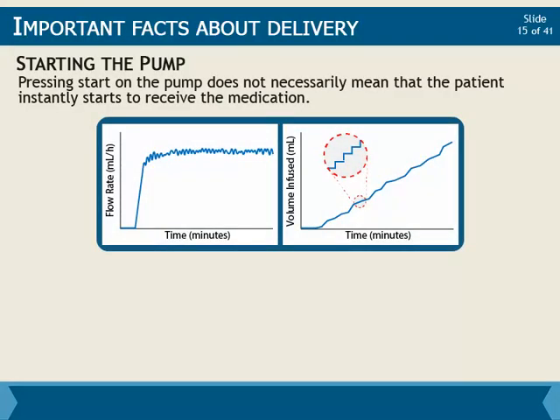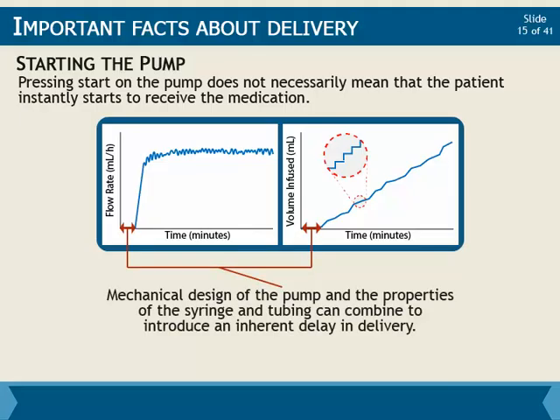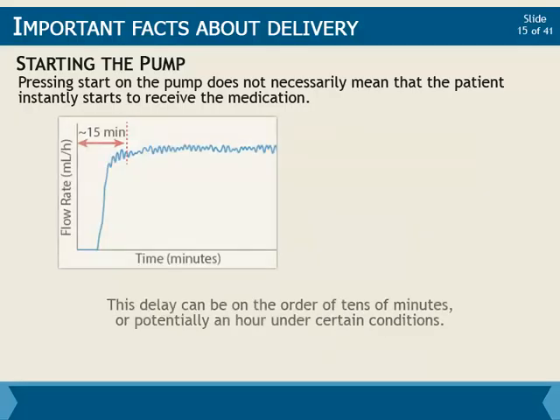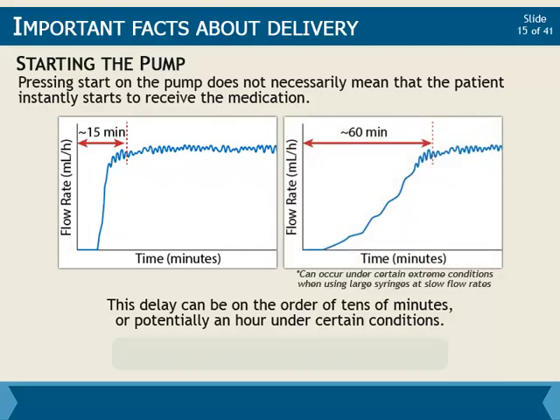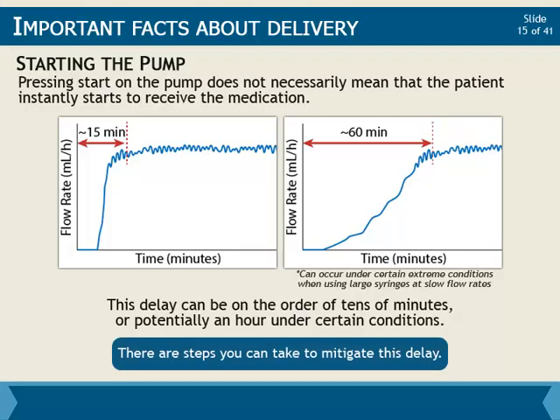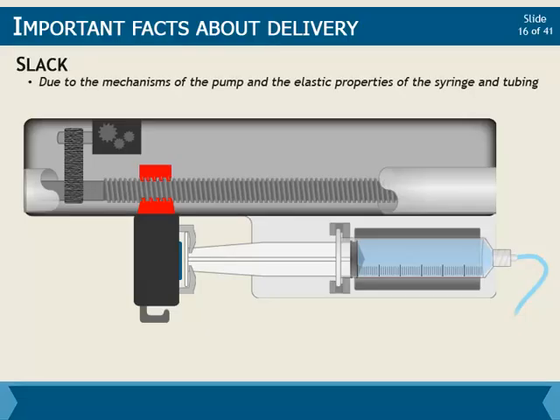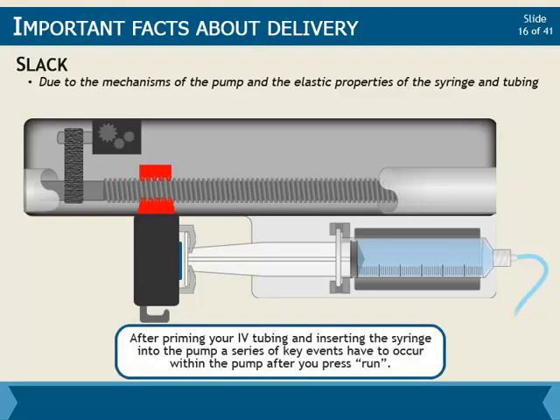Pressing start on the pump does not necessarily mean that the patient instantly starts to receive the medication. The mechanical design of the pump and the properties of the syringe and tubing can combine to introduce an inherent delay in delivery. This delay can be on the order of tens of minutes, or potentially an hour under certain conditions. But there are steps you can take to mitigate this delay. The delay is a result of slack due to the mechanisms of the pump and the elastic properties of the syringe and tubing. After priming your IV tubing and inserting the syringe into the pump, a series of key events have to occur within the pump after you press run. These events must occur before fluid will flow through the tubing and into the patient at the set rate.